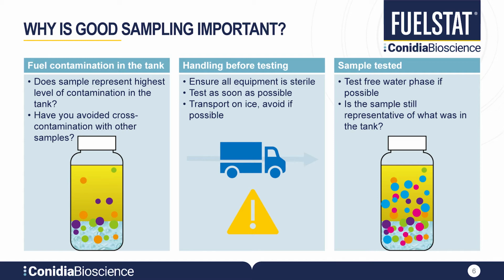The main reason is the longer it takes for the sample to be tested, the more likely organisms can be changed by either multiplying or, in a worst case scenario, they'll actually die. While having higher test results might not be the end of the world, as it would likely lead to some sort of intervention in fuel treatment, if the organisms perish and you end up getting a false negative result, that's not necessarily an ideal outcome. You would be operating under the belief that everything is okay and that no action needs to be taken when there could be a problem lurking around the corner.